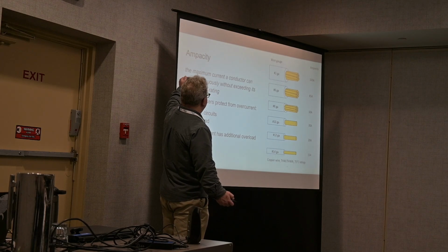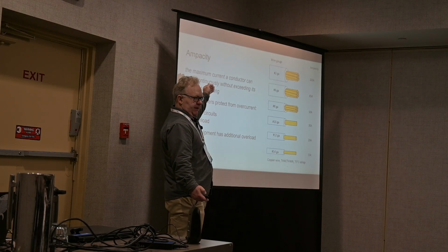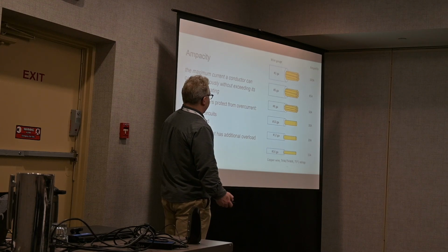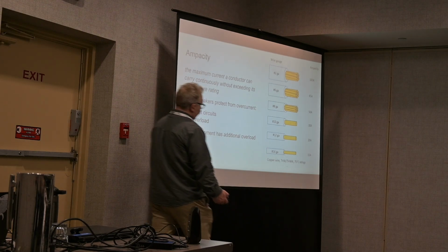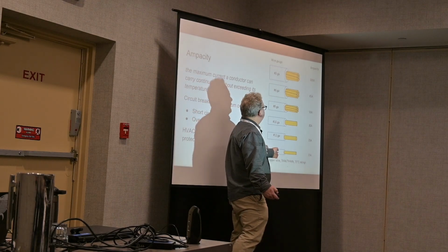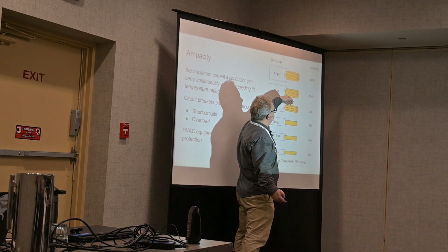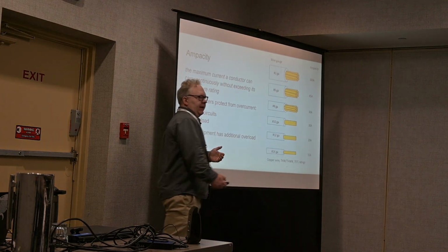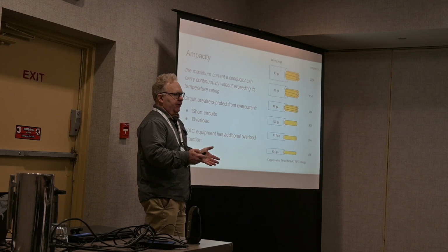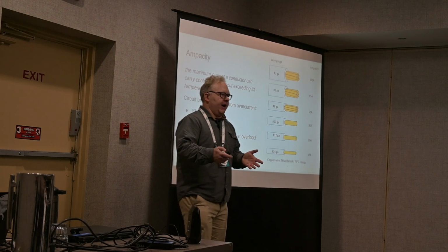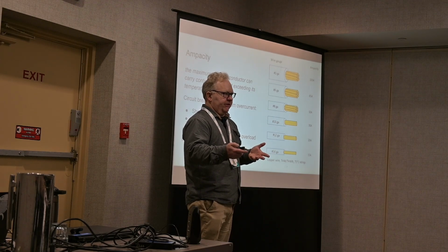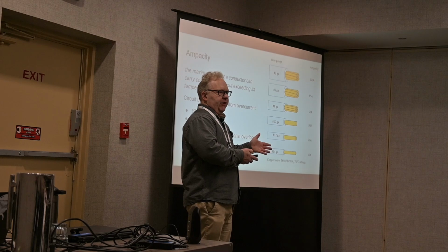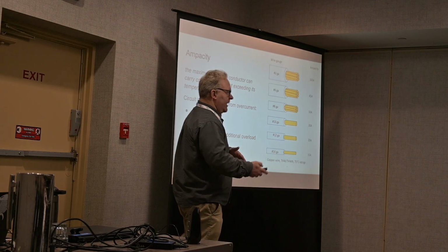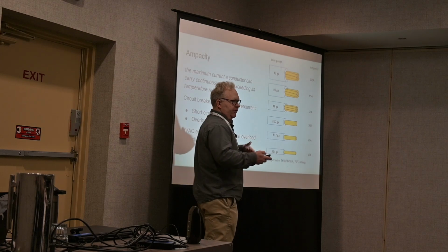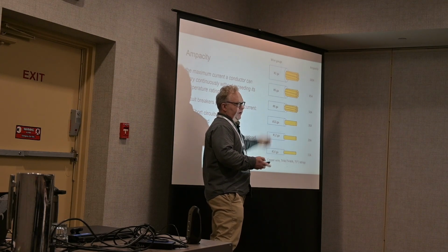Every conductor has a maximum safe current that it can conduct without overheating. And that depends on the size of the wire. The lower the gauge, the thicker the wire, and the more amps it can conduct safely. But it also depends on the temperature rating of the particular conductor. Some things like non-metallic wire have only a 60 degree Celsius temperature rating. Others might have a 75 or 90 degree temperature rating. And so you need to know that when you are looking at the charts to figure out which conductor you need for a particular application.